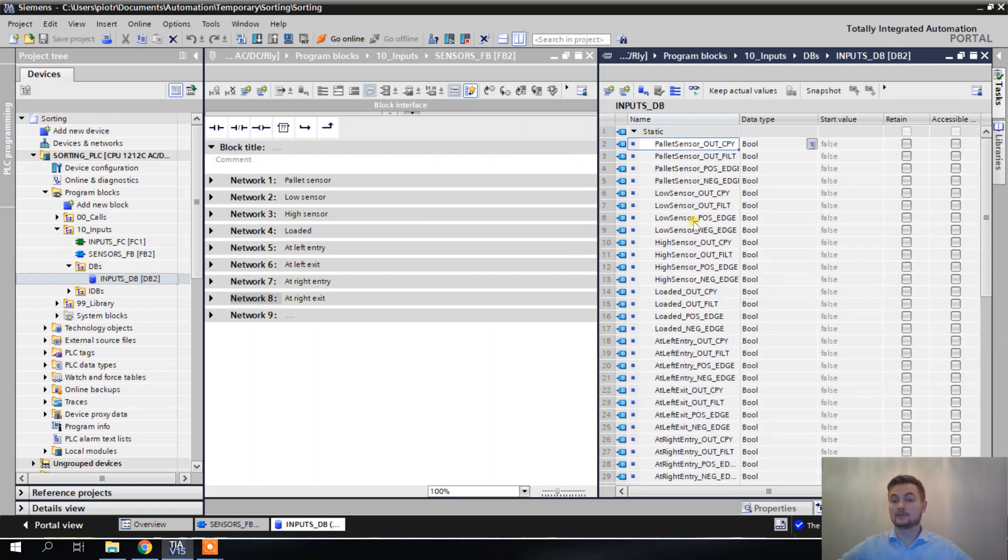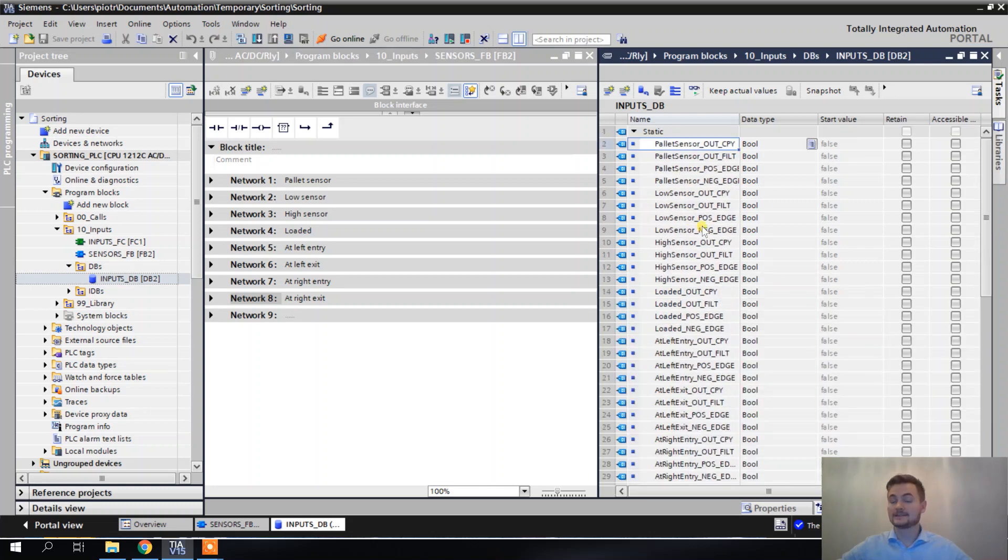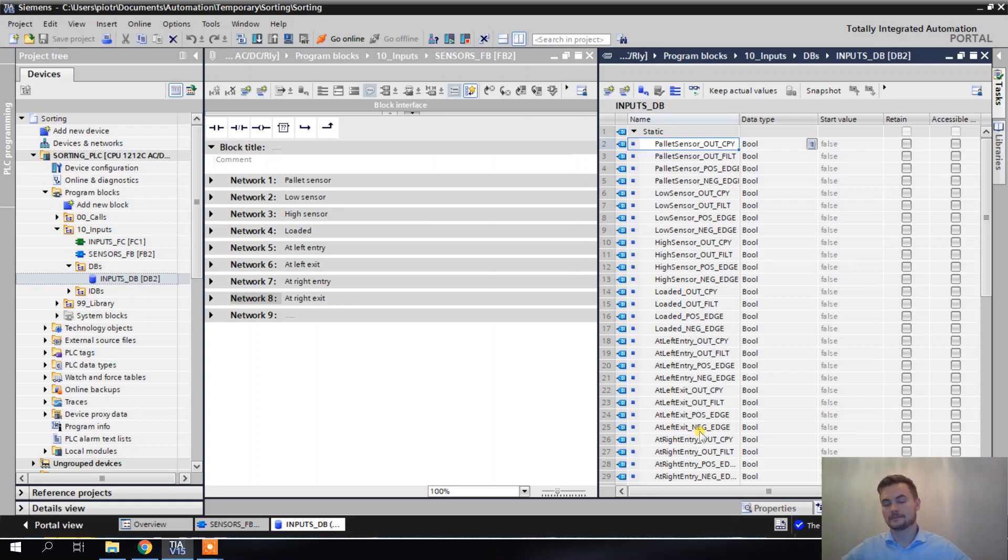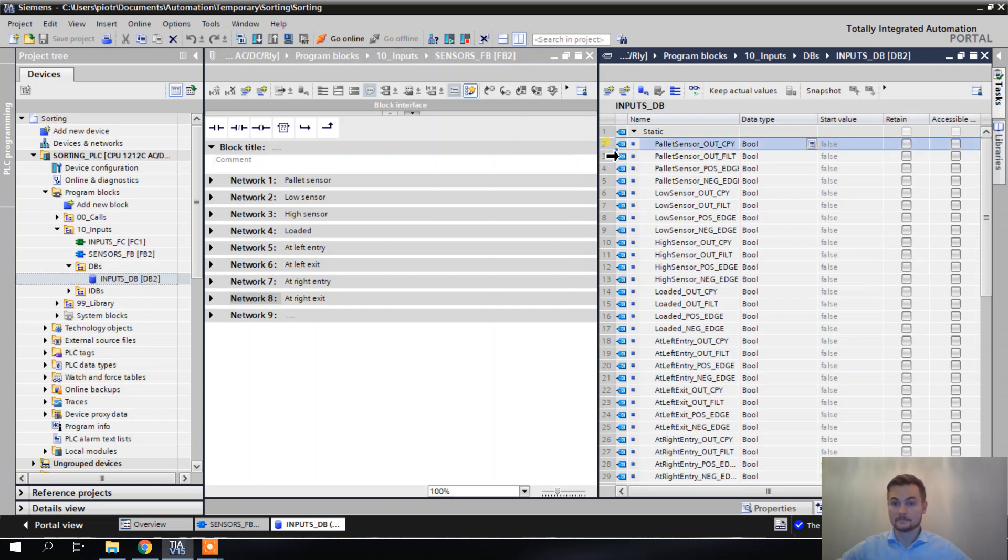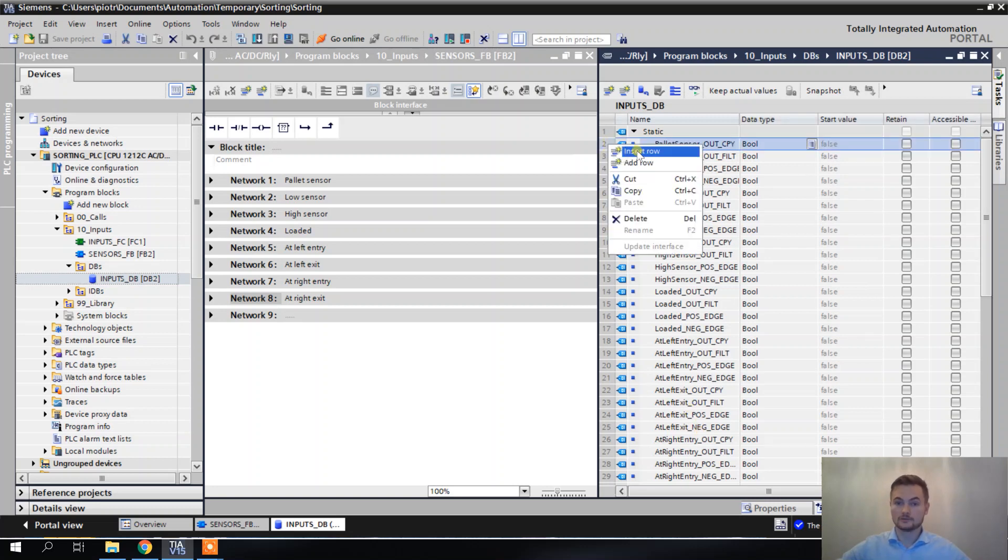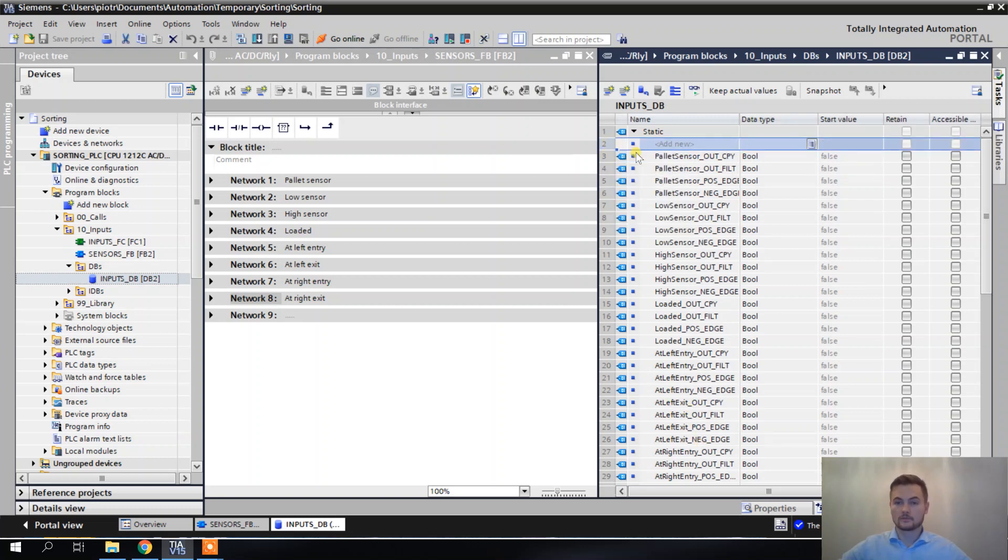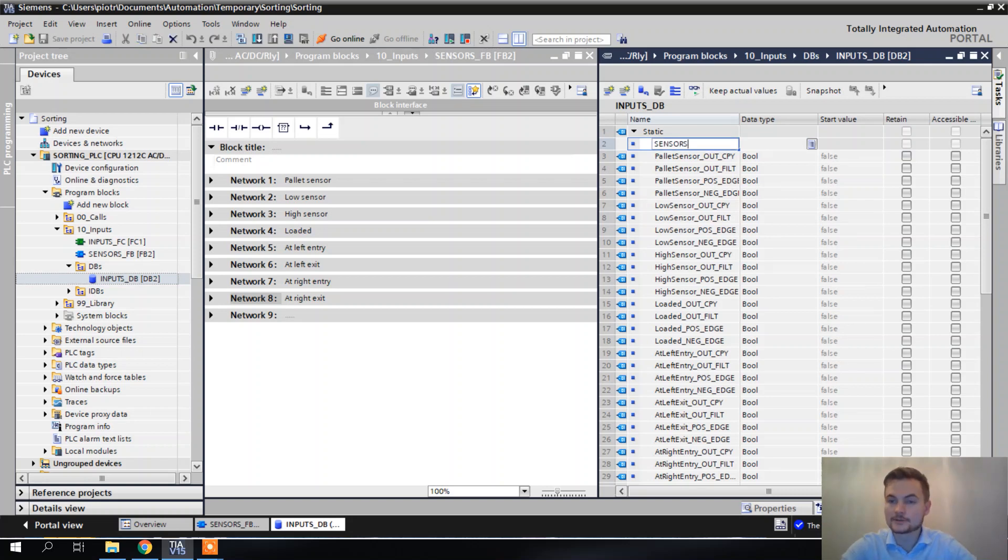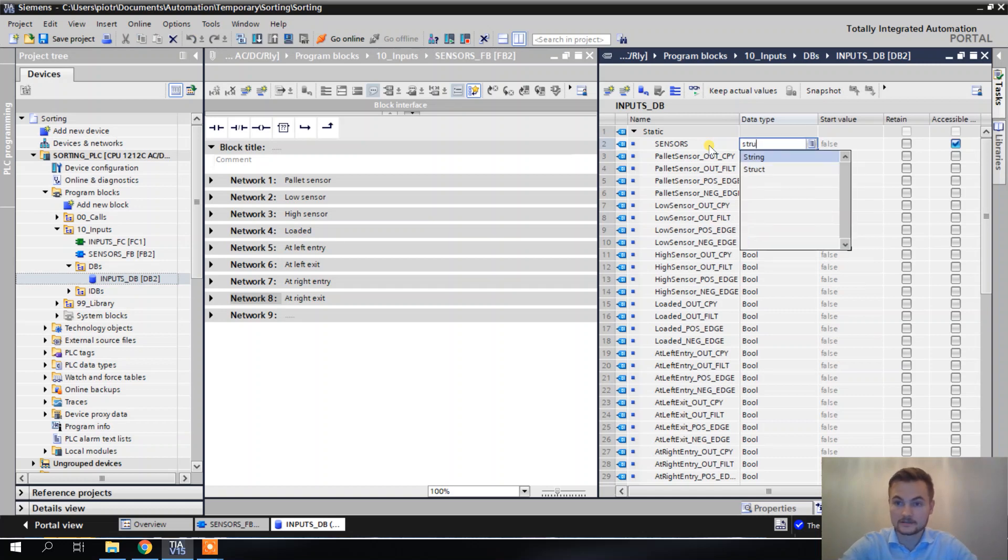That's why my idea is to put these sensors signal in a place where they will be a bit hidden, but still easily accessible. Luckily we can create such a place very easily. All we have to do, we have to add another tag here. I will name this tag sensors, and the data type of this tag will be struct, which stands for a structure.